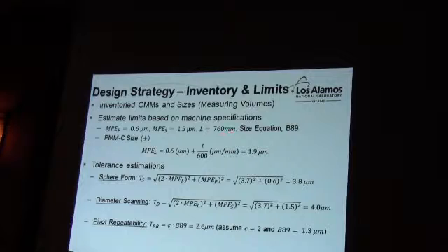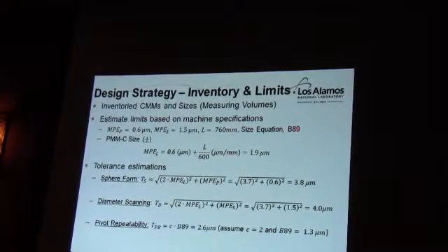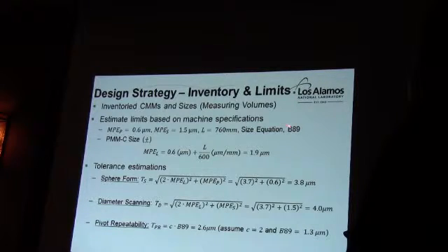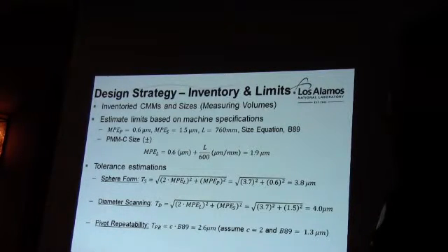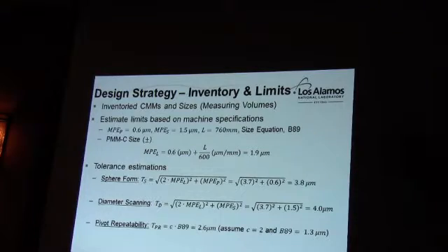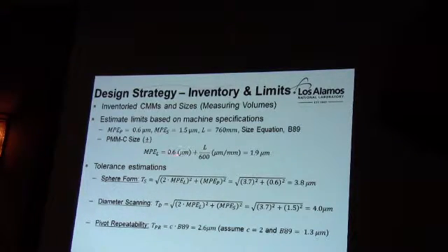And then we're using our size equation, which we call our MPE_L. This is basically from the 10360-2. Another thing we're looking at is the B89, B89.4.4, 10360-2008, I believe. It has an additional pivot repeatability test. We're using that also because this PMM-C sits on a pivot, and we're looking at some of the repeatability. So for the PMMC, we have a plus or minus. Basically, this is our MPE_L.